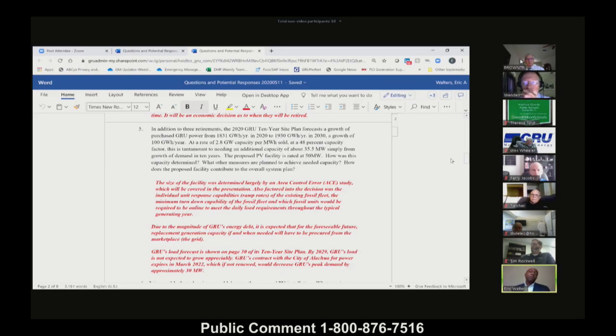Number one, being able to control it, and number two, being able to stay compliant with NERC guidelines. There were a number of scenarios run during that study, but effectively what came back from Burns and McDonnell was that 50 megawatts was about all we could handle with our existing generation configuration. Any additional will require something additional to go with it, some additional type of generation, either fast start or what have you.